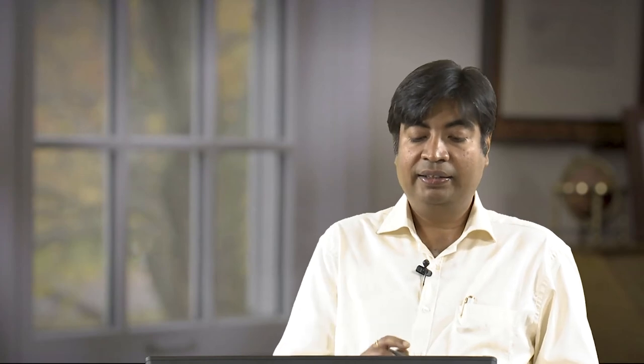Turn-off control is required, which is only possible with the GTO. A conventional thyristor could only turn off at current zero, not at the required instant when voltage is zero. Therefore, it is not always possible to replace the GTO with a thyristor. When a conventional thyristor valve turns off at zero current, it produces a full DC offset voltage on the capacitor, doubling the capacitor voltage across the thyristor. This increases stress on the valve and the time delay before the capacitor is again bypassed.